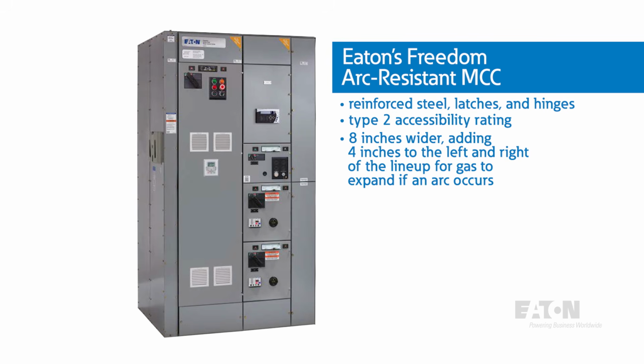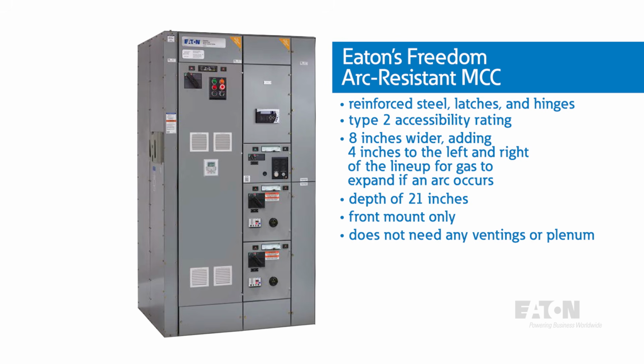The width of an arc-resistant MCC is 8 inches wider than a standard MCC, with 4 inches added to the left and to the right of the lineup to allow for gas to expand if an arc occurs. The depth of the MCC is 21 inches and is front mount only. The Freedom arc-resistant MCC does not need any venting or plenums to vent the gas, allowing it to be mounted up against a wall or a ceiling to be brought down to the top of the MCC.